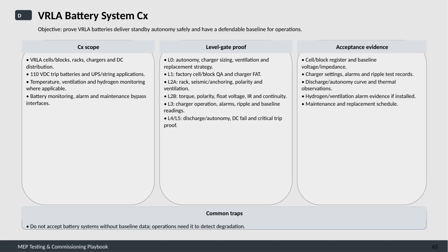For acceptance, evidence must include detailed records like the cell and block register, with baseline voltage and impedance, charger settings, along with alarms and ripple test results. Discharge and autonomy curves along with thermal observations support the performance evaluation. If hydrogen or ventilation alarms are installed, their functionality must be verified with evidence. A maintenance and replacement schedule should also be in place to support ongoing battery health.